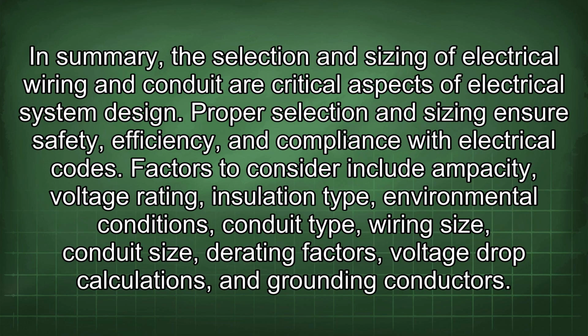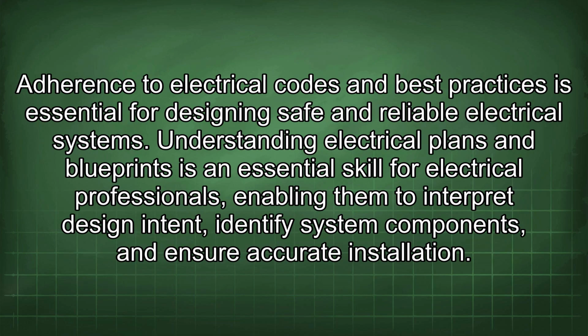In summary, the selection and sizing of electrical wiring and conduit are critical aspects of electrical system design. Proper selection and sizing ensure safety, efficiency, and compliance with electrical codes. Factors to consider include ampacity, voltage rating, insulation type, environmental conditions, conduit type, wiring size, conduit size, derating factors, voltage drop calculations, and grounding conductors. Adherence to electrical codes and best practices is essential for designing safe and reliable electrical systems.